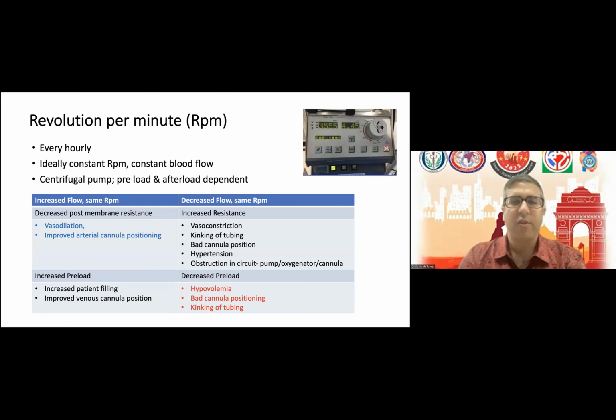So in the below table, I've highlighted if there is a decreased flow with the same revolutions per minute, that means there's either increased resistance or decreased preload. So decreased preload can be because the position of the cannula might have changed. There can be hypovolemia or there can be kinking of tubings. Whereas in case of increased resistance, again vasoconstriction, kinking of tubing, hypertension or obstruction in the circuit may be there.